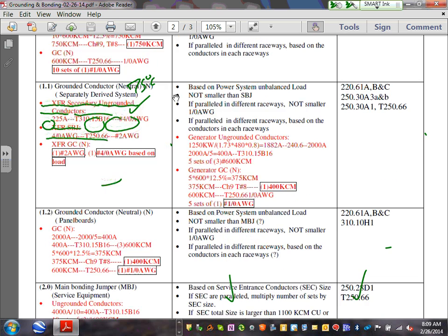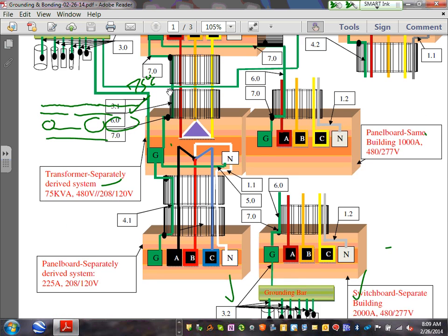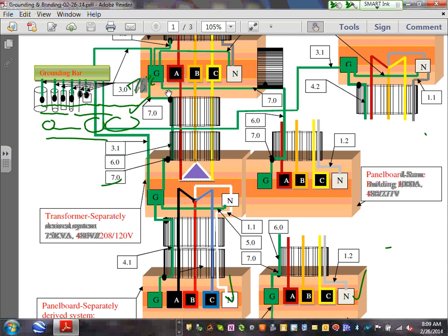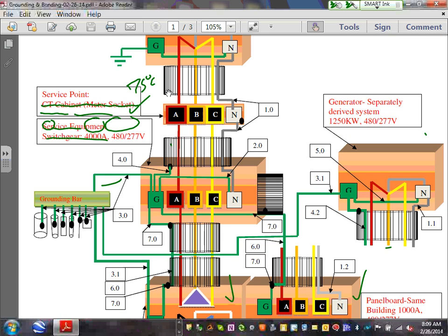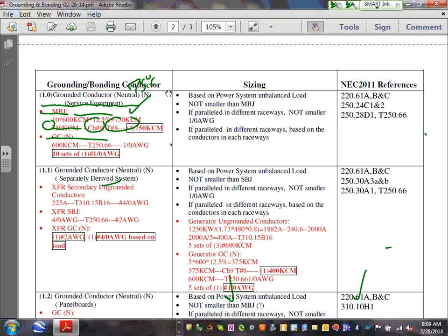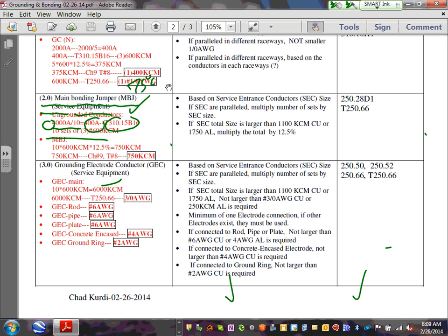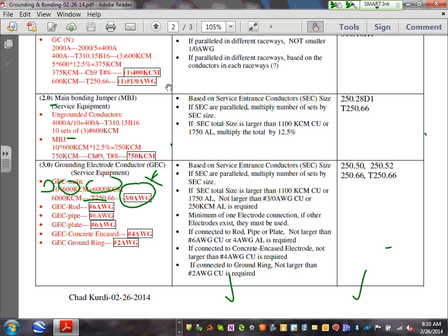Okay, so the 3rd thing that we need to do, guys, I'm going to go directly into number 3. Do you see number 3 is 3.0, the grounding electrode conductor. So Derek, my friend, the grounding electrode conductor, very easy, very simple. You take the number of sets multiplied by the size, give you 6,000, take it to table 250.66, give you #3/0 AWG. So that grounding electrode conductor does not need to be more than #3/0 AWG.